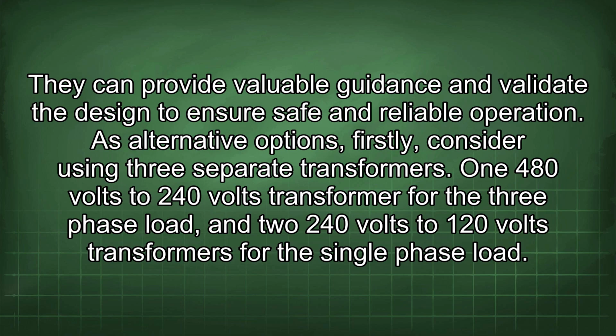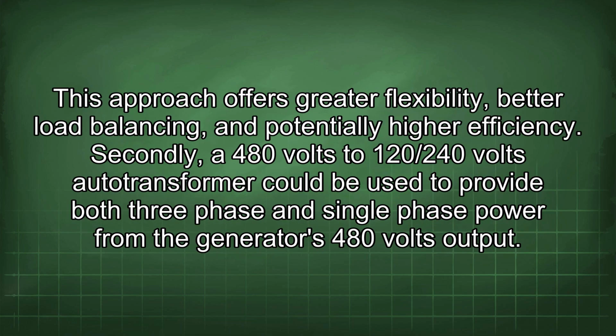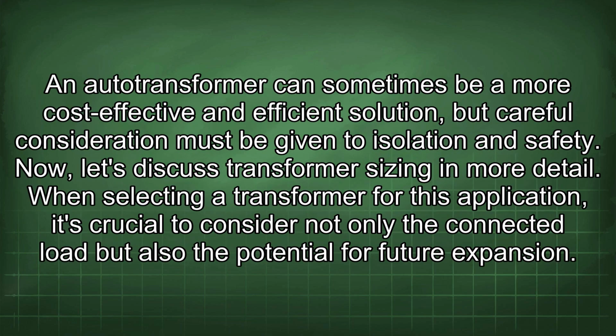As alternative options, firstly, consider using three separate transformers: one 480 volts to 240 volts transformer for the three-phase load, and two 240 volts to 120 volts transformers for the single-phase load. This approach offers greater flexibility, better load balancing, and potentially higher efficiency. Secondly, a 480 volts to 120/240 volts autotransformer could be used to provide both three-phase and single-phase power from the generator's 480 volts output. An autotransformer can sometimes be a more cost-effective and efficient solution, but careful consideration must be given to isolation and safety. Now, let's discuss transformer sizing in more detail.